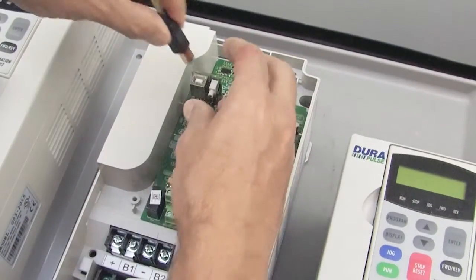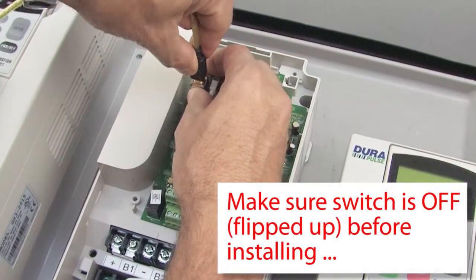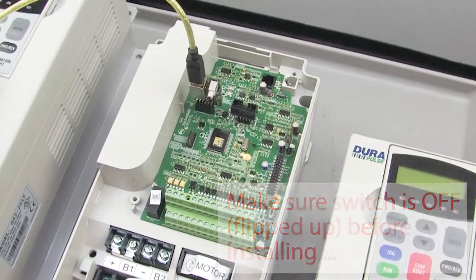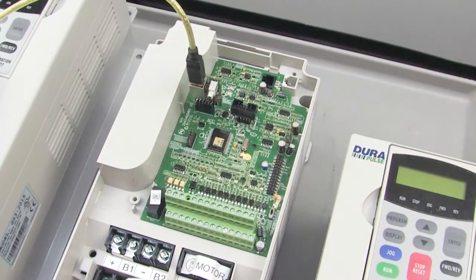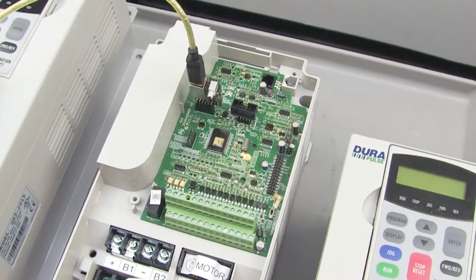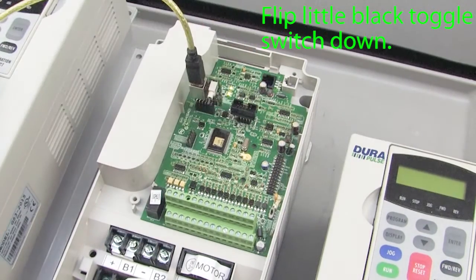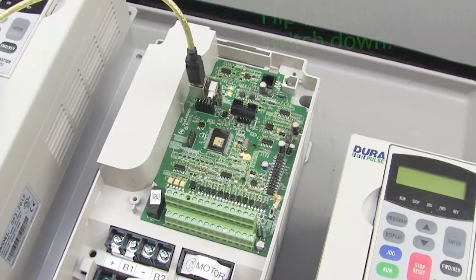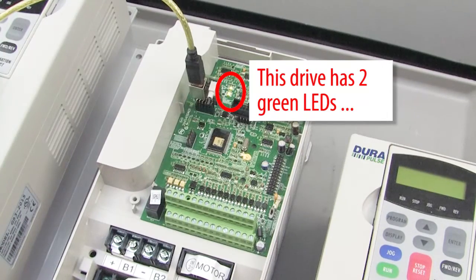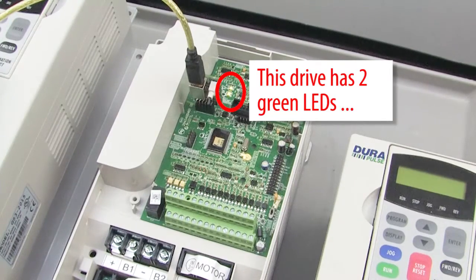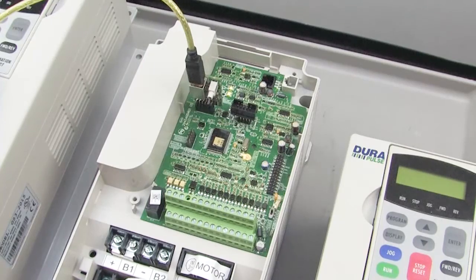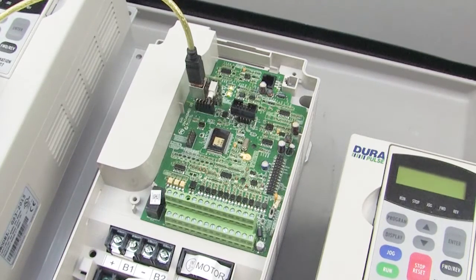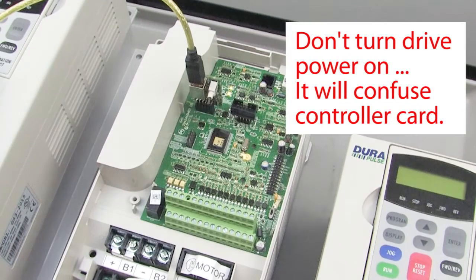Connect the USB cable between the PC and the adapter. Make sure there aren't any hubs, laptop docking stations, port replicators or any other device between the PC and the adapter. Turn the adapter's power switch on. You should see at least one green LED light up on the controller board depending on which size GS3 drive you are using. This switch applies the USB 5 volts to the controller card in the drive. And that's all the power we need. If you turn the drive's power on, it will also try to drive the 5 volt bus which will confuse everything.